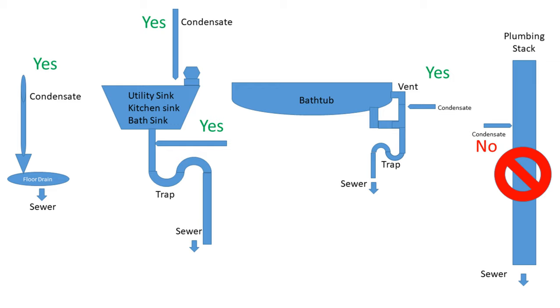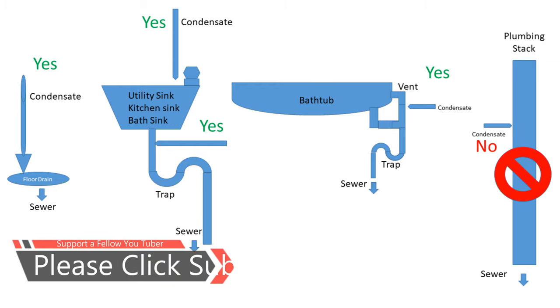The wisest thing is to look at your local codes to see what they accept for condensate discharge. My least favorite option is discharging outside the house — obviously you can do damage to your foundation. To summarize: first favorite is the floor drain to sewer; second favorite is the bathtub, which has the largest area to accept backed-up condensate; third is a utility sink; next is the kitchen sink; and last is the bathroom sink.